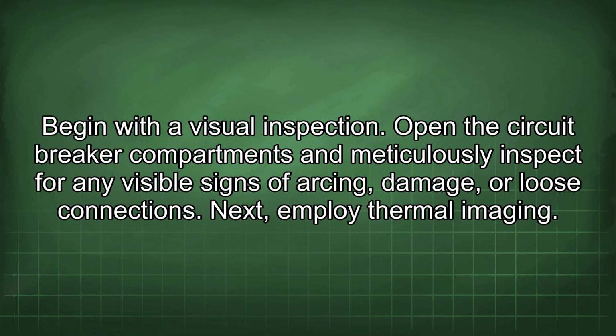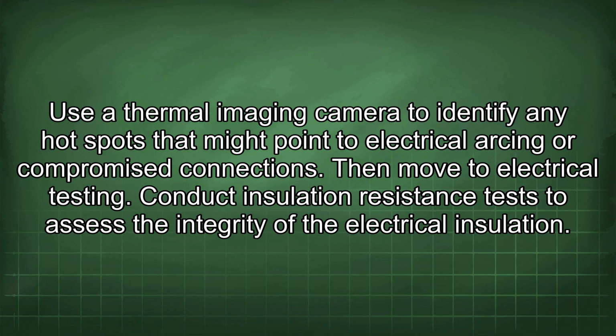Begin with a visual inspection. Open the circuit breaker compartment and meticulously inspect for any visible signs of arcing, damage, or loose connections. Next, employ thermal imaging. Use a thermal imaging camera to identify any hot spots that might point to electrical arcing or compromised connections. Then move to electrical testing. Conduct insulation resistance tests to assess the integrity of the electrical insulation.